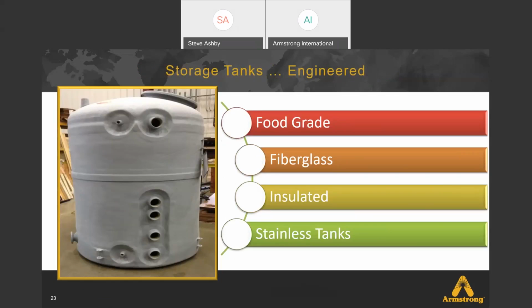Okay, tanks are critical when using direct contact heaters. Again, we generate the hot water, we need to move it to a storage tank. There are some applications where on the smaller heaters, you can make the bottom can of the heater itself a storage tank of sorts, but it's on the smaller heaters. Most of the times, a standalone atmospheric tank is part of the installation. We supply a lot of tanks.